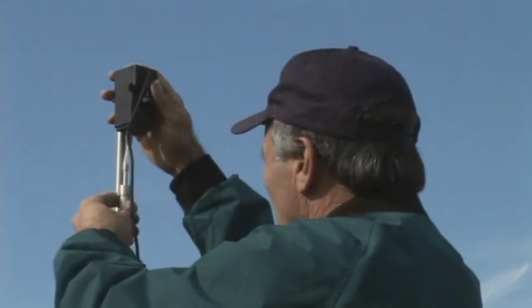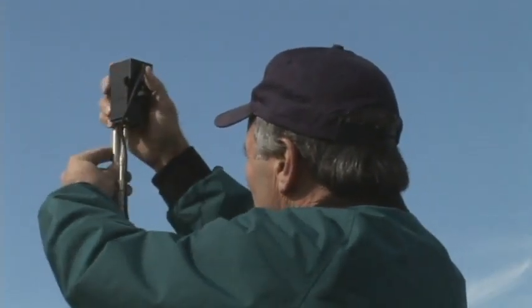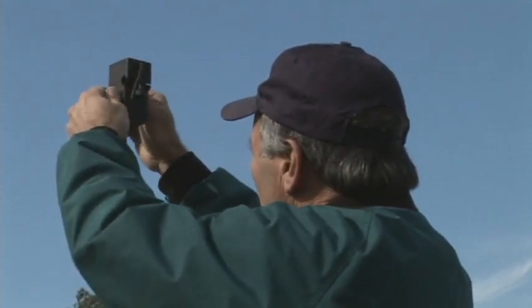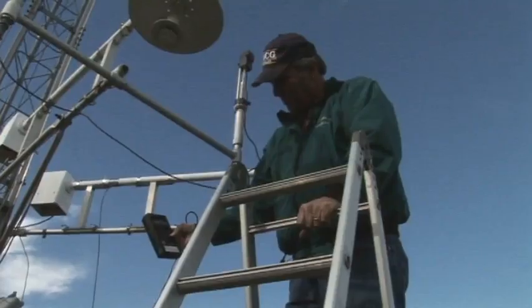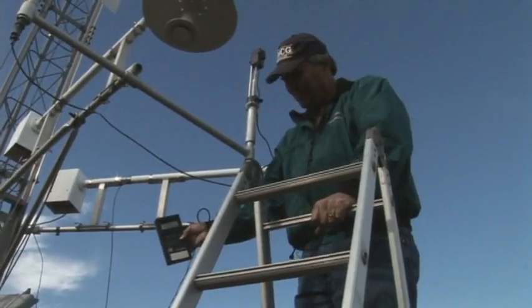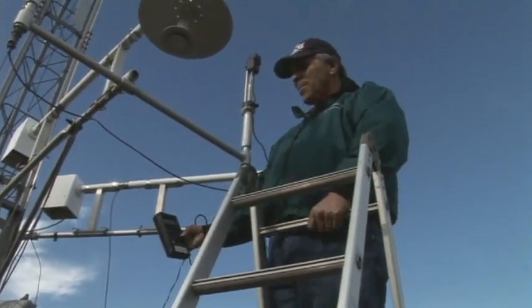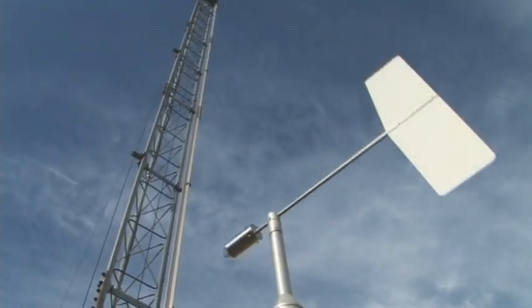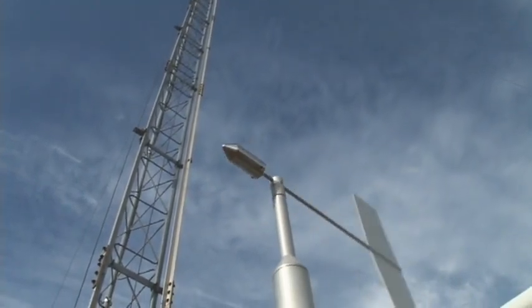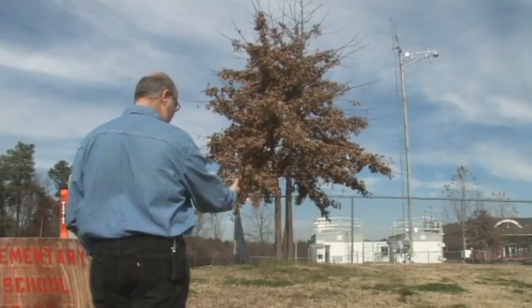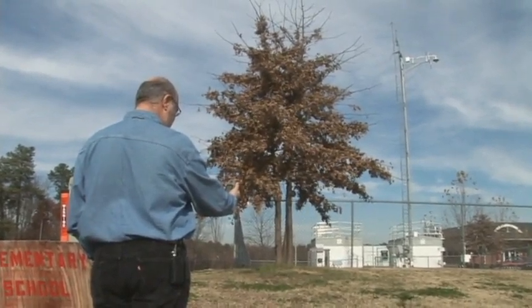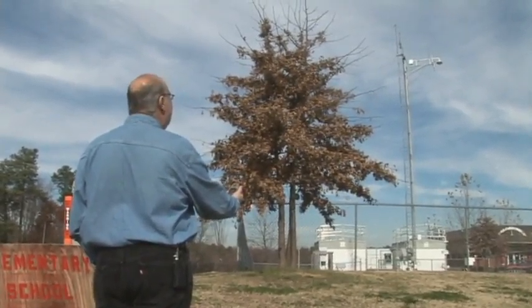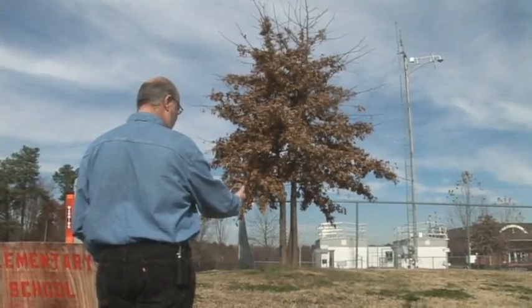Perform the maintenance on your sensor that is recommended by the manufacturer. It is recommended that once you connect the sensor back on the instrument boom and hook up the cables, that you rerun the 0 and 1 upscale point to make sure that all connections to the sensor have been connected properly. Our next task is the calibration of the wind direction system. If you remember from earlier, we used the GPS unit to reference the alignment of the instrument boom. We will now utilize this information to perform the wind direction calibration.